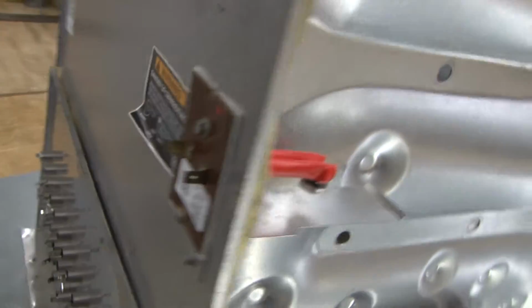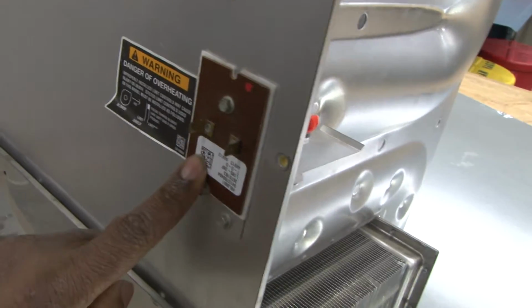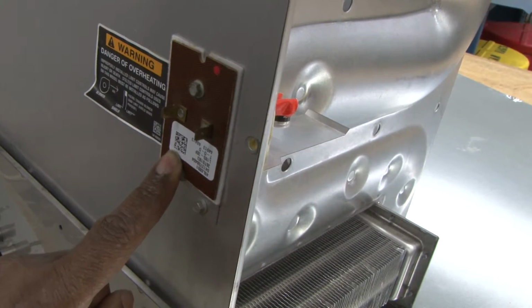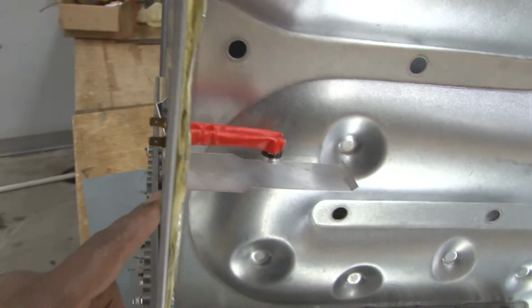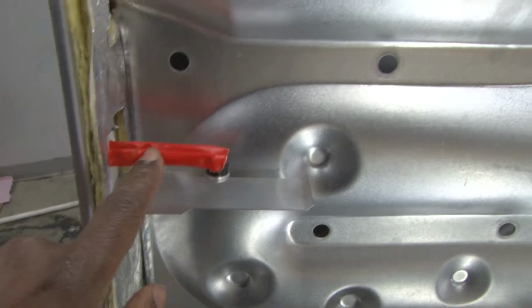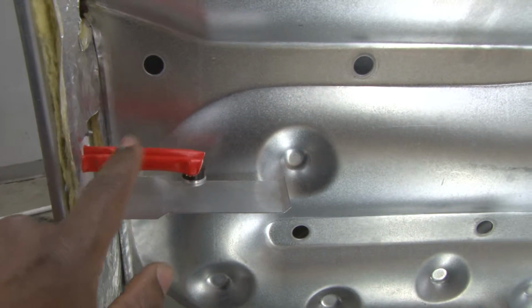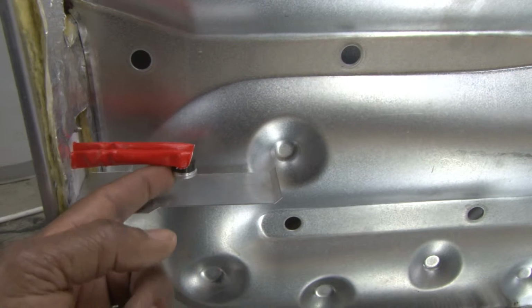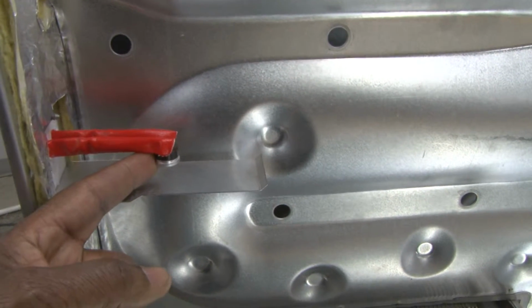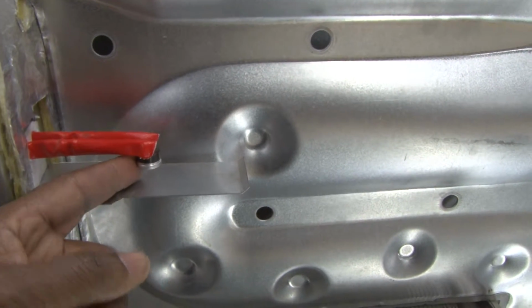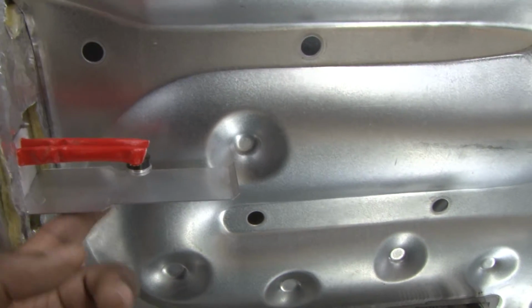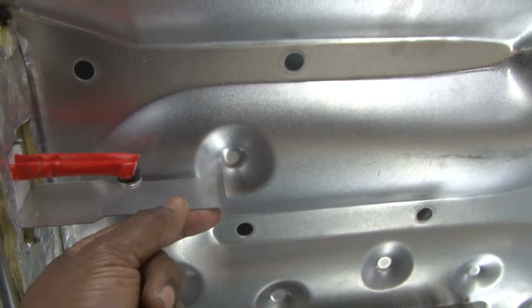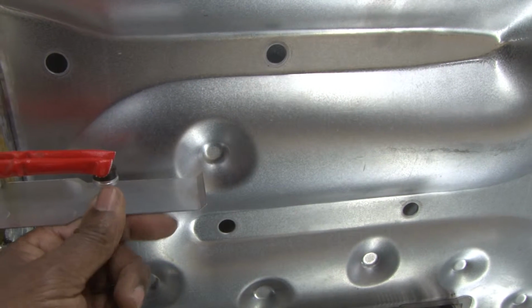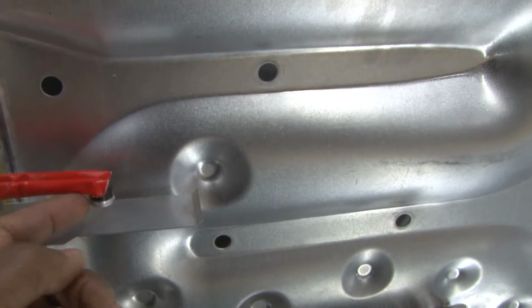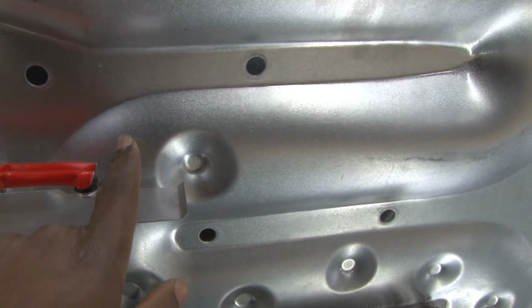To take a look at it, you can see where the high limit control is located, and we take a look on the inside of it. We see how it's extended and has a thermal disc which is sensing the heat from the heat exchanger. There's a plate there to deflect some of the heat rising, so it's actually sensing temperature from the heat exchanger itself.